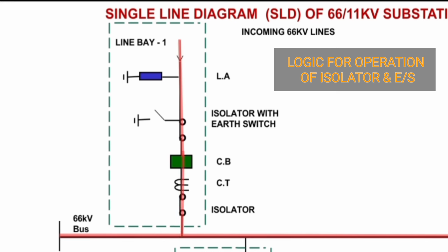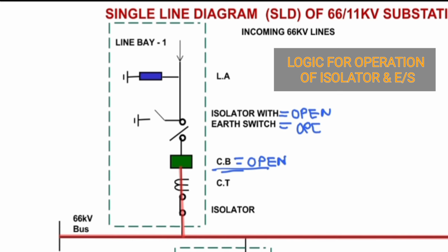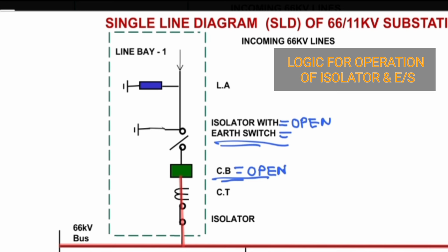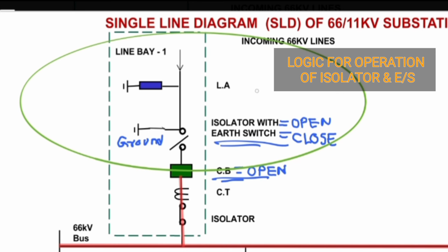In this condition, the circuit breaker is on and both isolators, that is the line isolator and the bus isolator, are closed. Also, the earth switch connected with the line isolator is open, as shown here. In this case, the circuit breaker is operated and made off. Also, the isolator is operated and made open. Then the current will be shown like this and the earth switches are open. Now let us perform the switching operation and close the earth switch. In this case, whatever charges were trapped in the line will be grounded. Now the area marked here is the safe working area, and maintenance work can be done very safely.